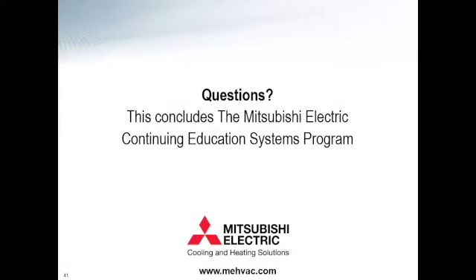Would it be possible to retrofit an existing PTAC system in a building as well then? Yeah, well, we can absolutely retrofit an existing PTAC system. Do you mean like on the water side without disconnecting existing piping? No, so really you can pair off the existing water loop that you have with a water side condensing unit, and then have that unit tied into the new HVRF system when it is available. And then that would be able to replace the PTAC, yeah. But there would still be a significant amount of retrofit piping and things like that. It wouldn't be as simple as plug and play with a water side Mitsubishi heat pump right onto the existing water loop.